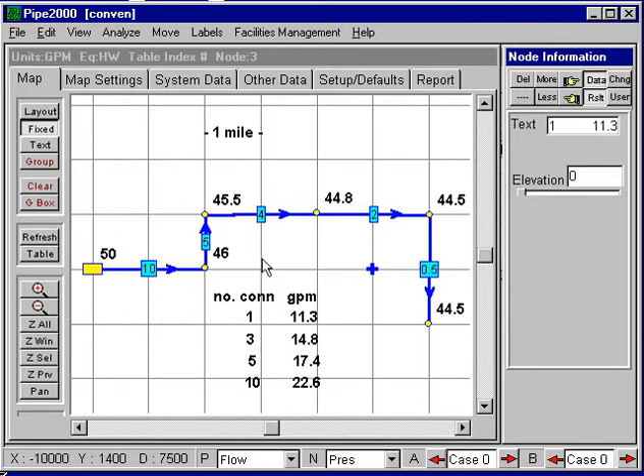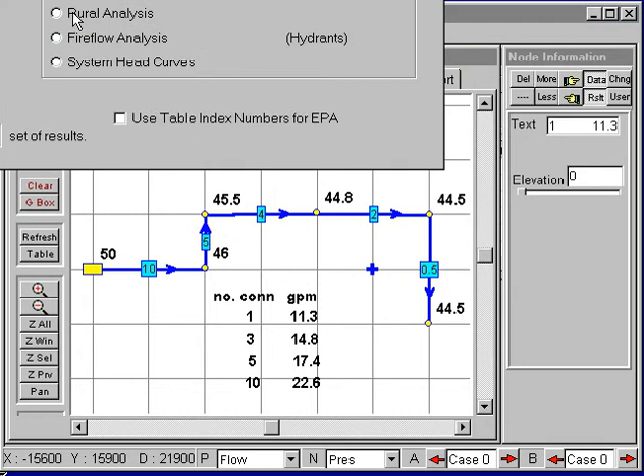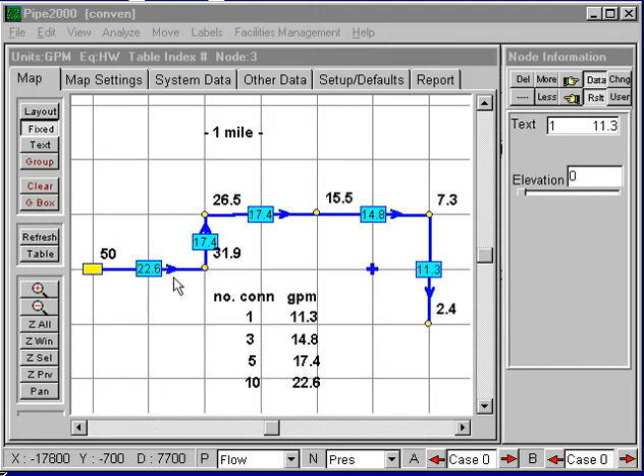I'm going to go through an alternate analysis using the rural program. I'll select rural analysis and analyze this. When this is complete, we see a totally different result. We have 22.6 gallons per minute because this line is serving ten users, and 11.3 gallons per minute because this line is serving one user. We have much larger pressure drops, and this is the result of doing the allocations based on the peak demand diversity curve.